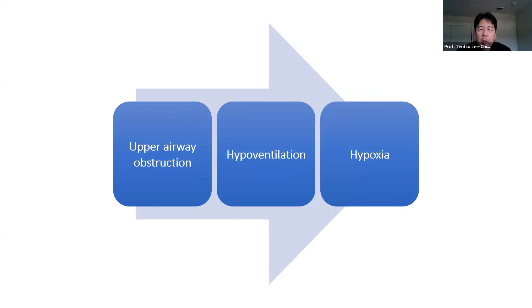And how do we address all of this? Well, for upper airway obstruction, we can use a CPAP or the EPAP of a bilevel. EPAP is a lower pressure of the bilevel device. For hypoventilation, we can decide to increase the rate if it's too low, or we can add the pressure support, the difference between the IPAP and the EPAP of a bilevel. And for hypoxia, in addition to providing oxygen therapy, we can change the rate if it's low. We can add EPAP to increase lung capacity or provide pressure support to augment tidal volume.